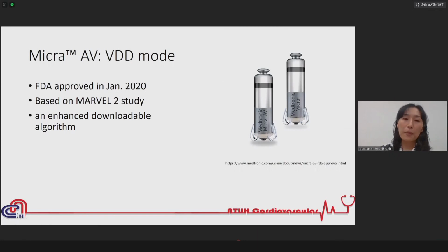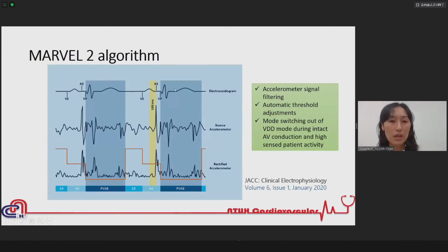We've been waiting for a DDD leadless pacemaker. This year FDA approved the first model, MICRA AV, with VDD mode, based on the Marvel 2 study. It's a downloadable algorithm called the Marvel 2 algorithm, featuring enhanced accelerometer filtering, automatic threshold adjustment, and mode switching between VVI 50 and VDD mode.